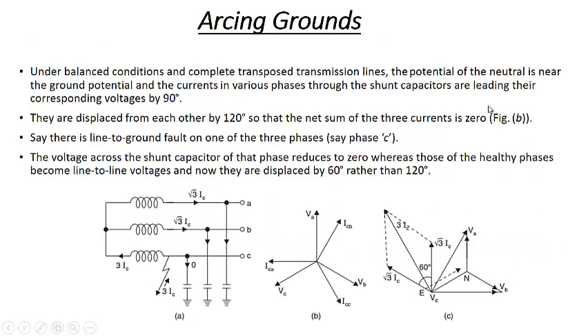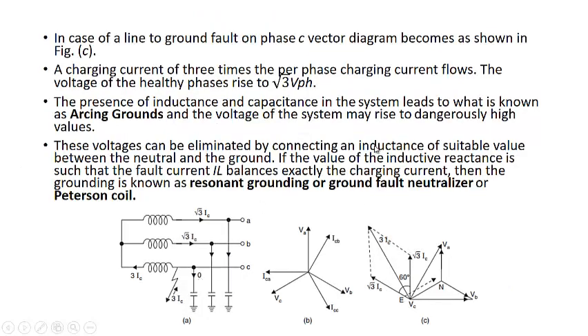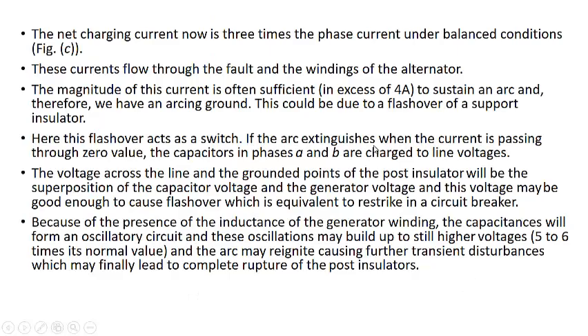This arc will be sustained between the healthy phases and the ground. It may result in the ionization of the air. That's what is meant by an arc. Therefore, such a condition is denoted as arcing ground, because it produces an arc between the healthy phase and the ground because of this charging current. This could be due to the flashover of the supporting insulator. This arc is sustained because of the flashover of the insulator.